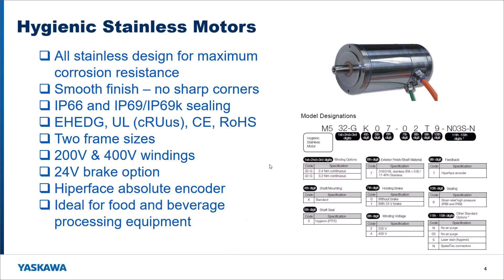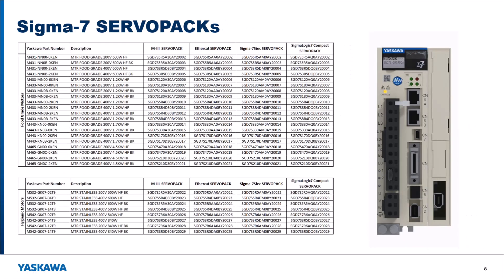Currently we have two frame sizes launching — the 2.4 newton meters and the 3.2 newton meters continuous — with another two frames in development. These hit 70 to 80 percent of the applications you're going to see for these types of motors, so we think this will be a pretty good offering to start. We have 200 volt and 400 volt windings, a brake option, the same Hiperface encoder, and these are specifically made for food and beverage processing and packaging.